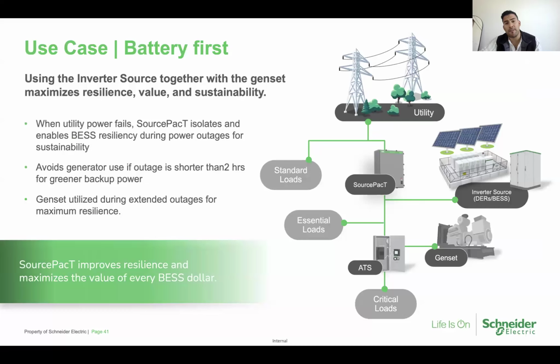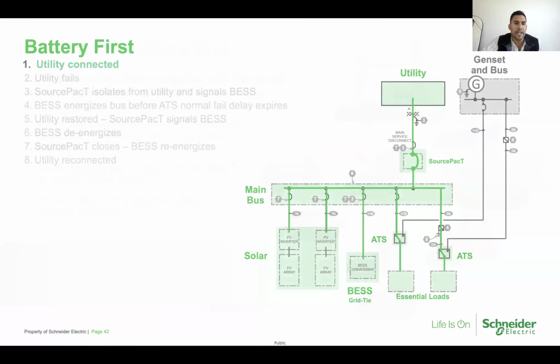Now we'll go through a battery first scenario. This is a use case where you have your energy storage system connected to your main switchboard. SourcePacT serves basically as the service disconnect, downstream of the service disconnect, and downstream of that main switchboard you'll have your generator. This is where you have that N+1 scenario where you can call in the battery energy storage system first to provide backup power. And of course, if that energy storage system were to deplete its reserve, you have the generator there to kick on as a secondary emergency power source, where the ATS is at that point transferred from source 1 to source 2.